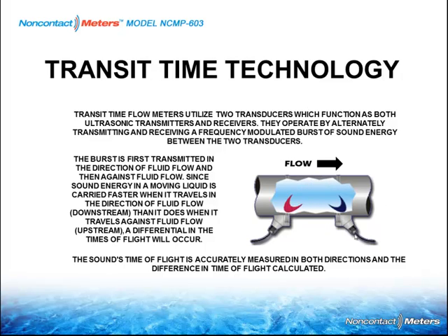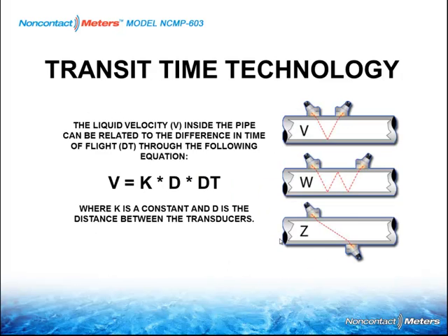The sensor on the right hand side here is going to, at the same time, send a sound burst across the pipe here, reflect off the back, come downstream here, and because it's going against the current, it will take a longer period of time to transit the pipe. The greater the differential, the higher the flow rate. And this is how it works. Now the positioning of the ultrasonic transit time flow meter obviously plays a role because we're measuring the transit time and the distances between 2 points.